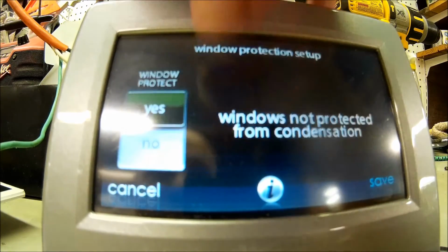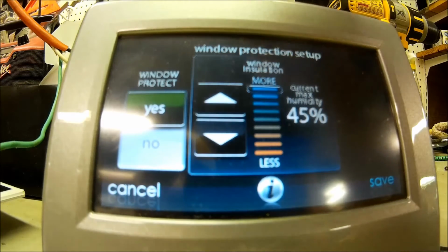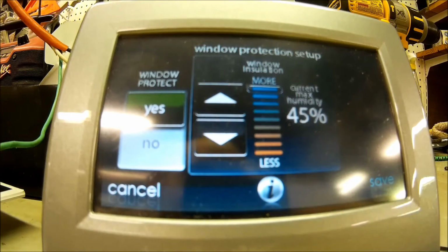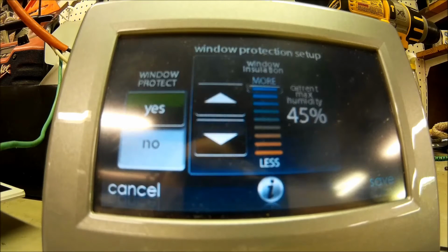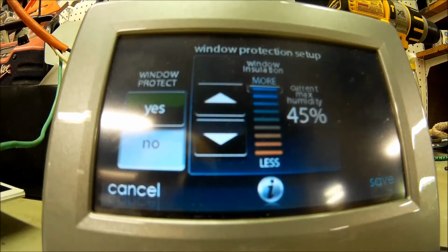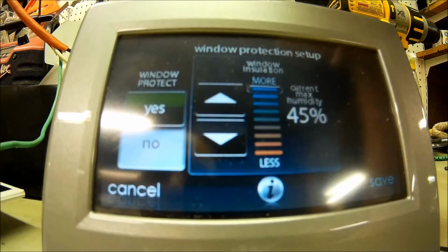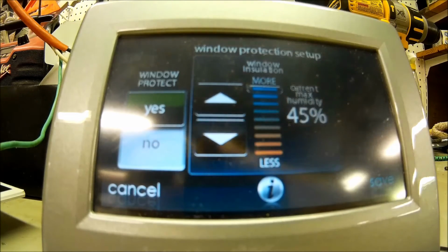Window protection setup, that's for humidification. It's like auto humidify. Usually when we set these systems up, we're doing a whole system where the temperature probe is in the outside air conditioner, and the humidity will be regulated off outside temperature. So if you have window protection on, it's going to automatically humidify to 45% depending on the outside temperature, no matter what you have the manual set up to do.